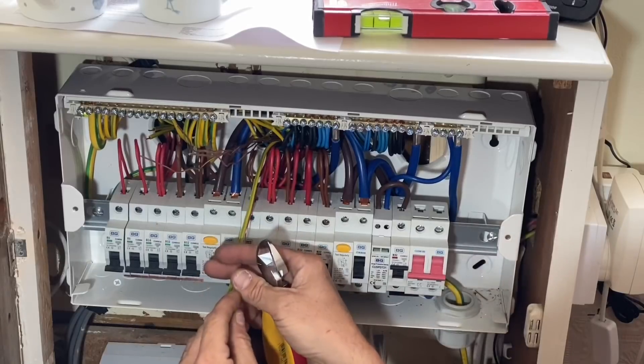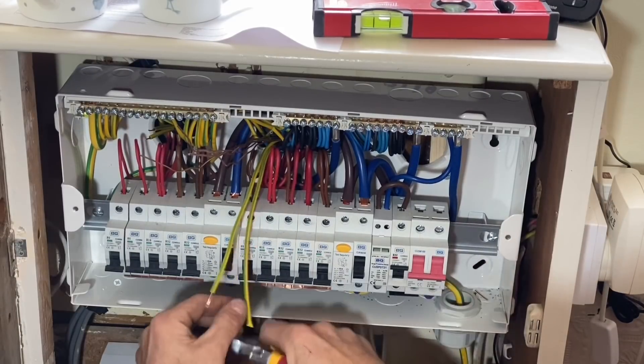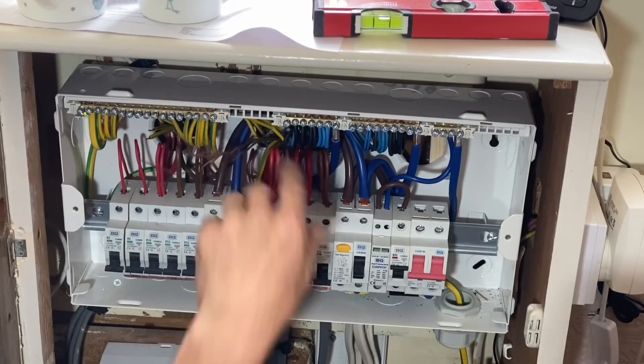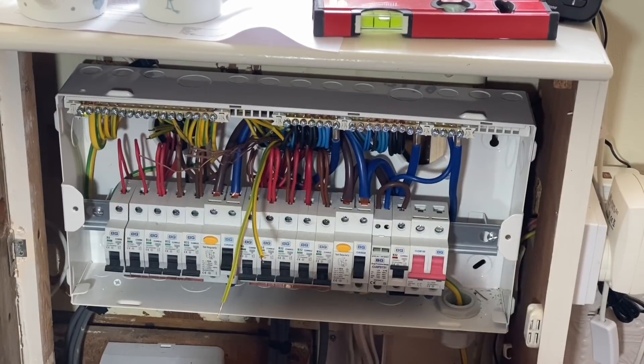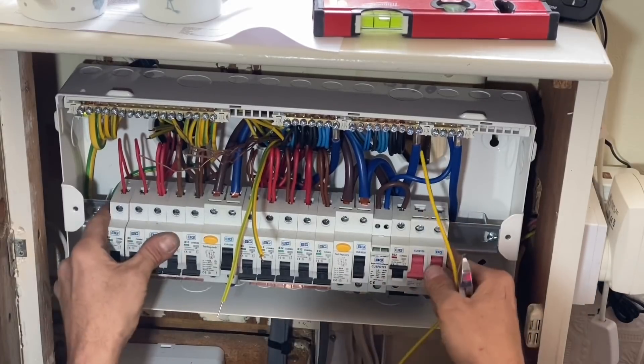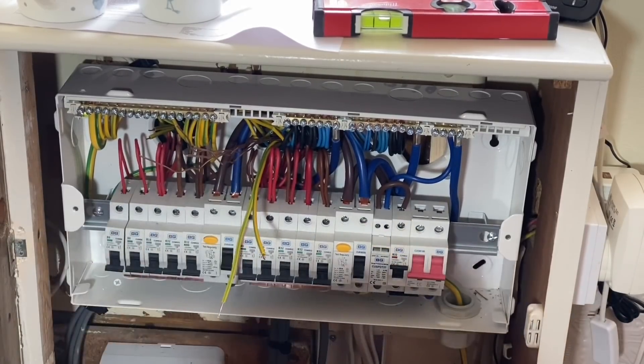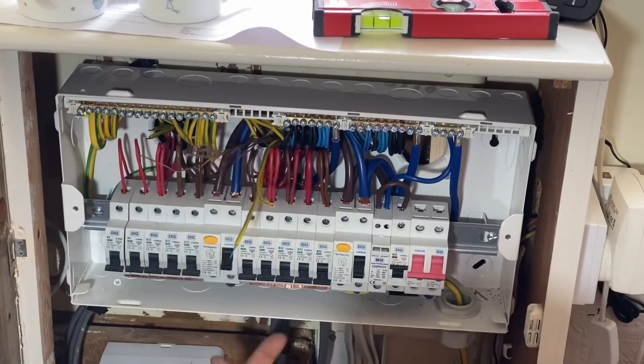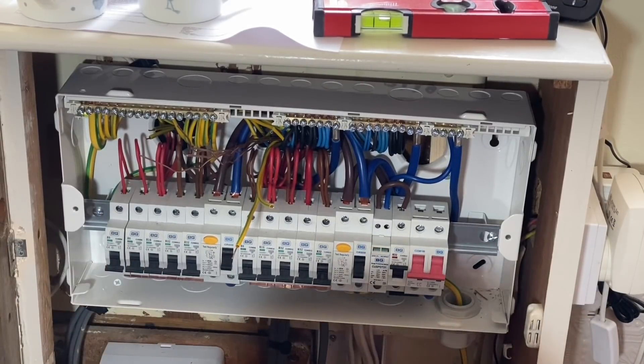We're coming towards the end — CPCs going in before we go off testing. What would be your feedback for BG on their boards? Not everything's perfect — no board is. There are a few little downsides: one being the knockout for the tails isn't in line, so I've drilled my own here, but it could do with having a knockout there. Also the DIN rail — this one is solid because I've dressed the cables in properly and it's screwed decently — that's not going anywhere. But I have had them lean forward with the weight on them in the past, so maybe just one more solid attachment in the middle of the DIN rail would stop that happening. You do also get issues with the lid, and I think that's down to the rail — if that's sorted it would take that element away. So yeah, not perfect, but it's definitely one of my favourites to work on.